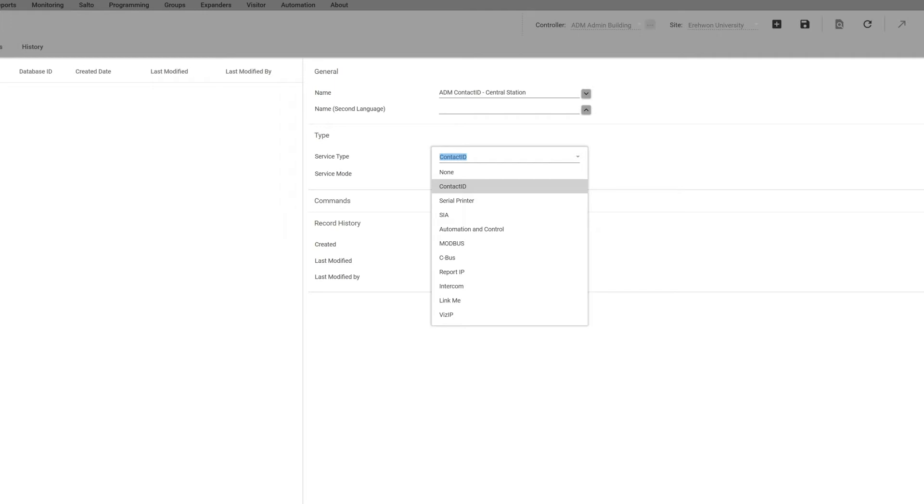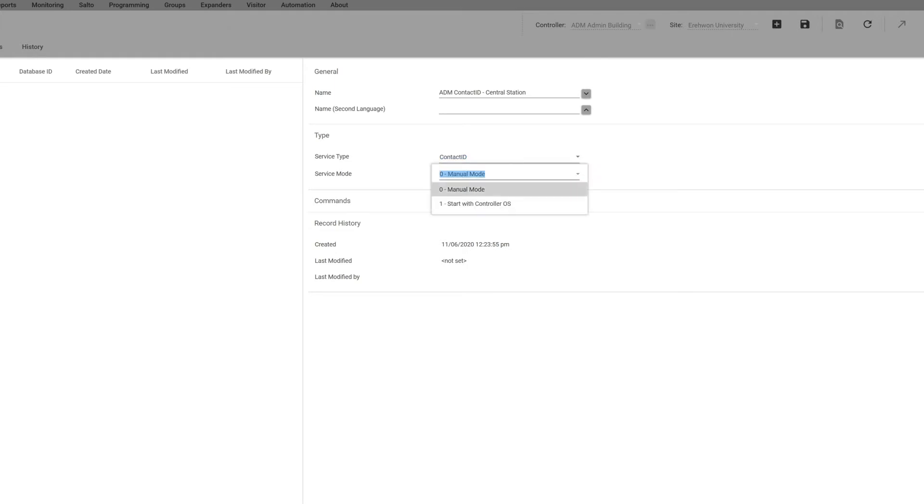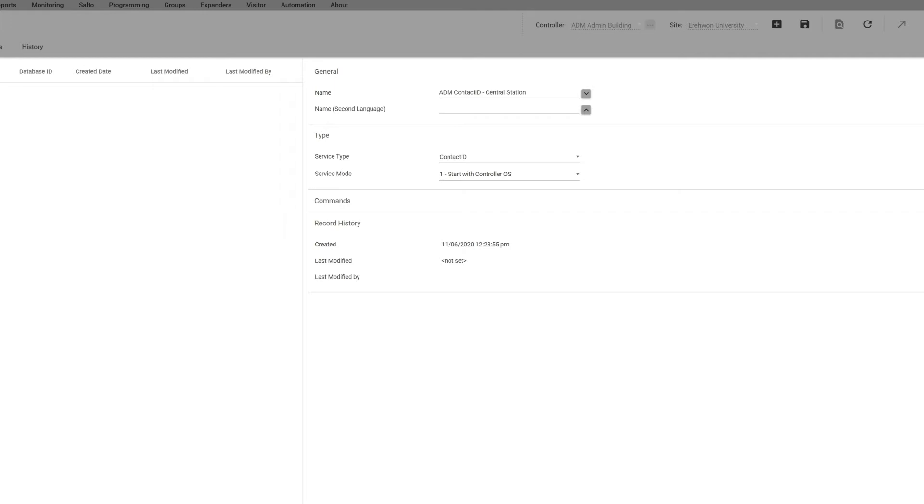The service mode here, the default is manual mode. What that means is if the controller ever goes down like the power goes down and then it comes back on again, you would have to manually restart the service every time. We recommend that you do the other one, so when the controller goes down and restarts again it will restart that service when it goes back on.